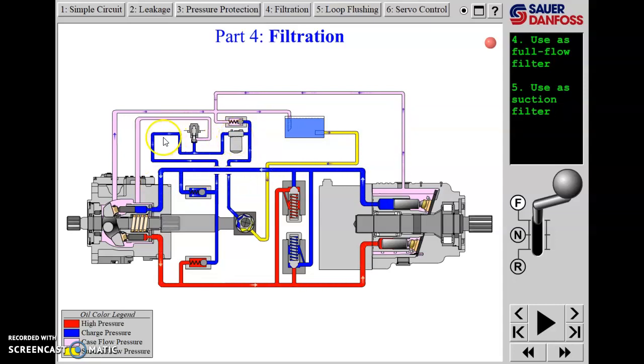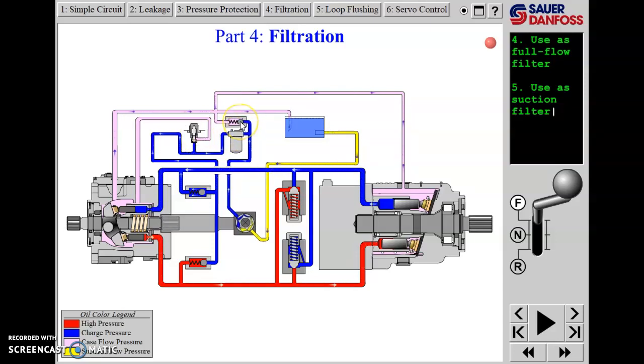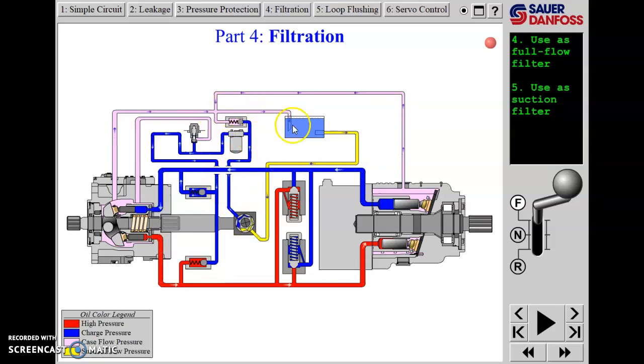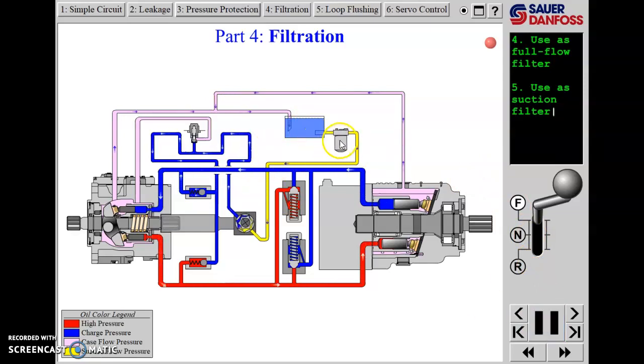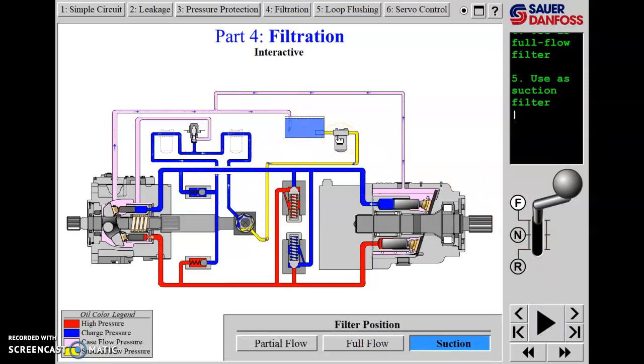Either way, it's getting filtered. However, we don't have any pressure protection here. When the filter was in the previous location, the charge relief was also acting as filter restriction protection. Here they had to add another relief valve essentially parallel to the filter, in case the filter gets fully restricted.